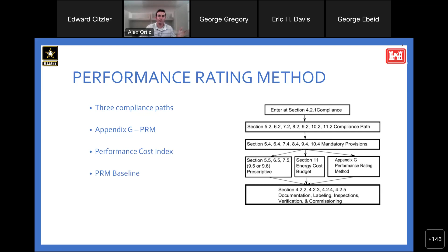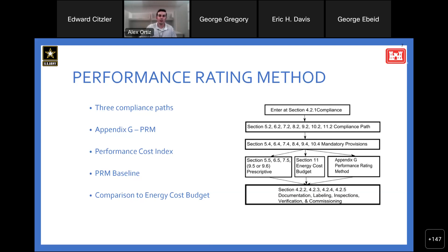Compared to the energy cost budget, which was previously the performance path, this new path takes the minimum prescriptive requirements from the 2004 version of ASHRAE, whereas the energy cost budget takes the minimum prescriptive requirements of the current version of ASHRAE. So you would think it would be easier to meet this path of compliance since it's using older, worse efficiencies from 2004. However, as I'll get into in more detail with our methodology and our analysis, they apply certain factors and change the equation, which makes it slightly more difficult to achieve compliance with this new PRM path of compliance.